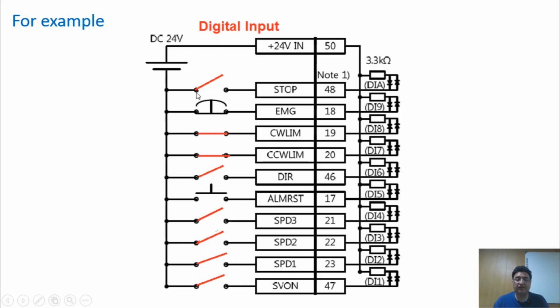If we set digital input 48 to operate as normally open, meaning its fundamental logic is normally open, then whenever we connect a standard 24-volt voltage to this terminal, according to this circuit diagram, the terminal will be activated. Based on the functions we have assigned, terminal 48 will then perform a specific, predetermined task for us.